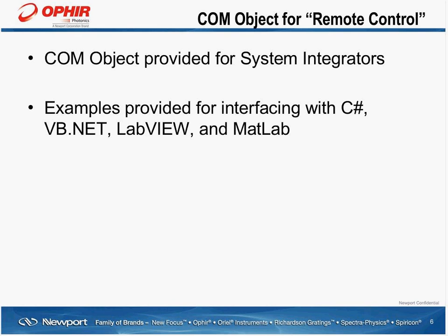I mentioned very briefly at the beginning, I'm going to mention it now slightly less briefly. The important feature of StarLab is the Ophir COM object. This replaces what used to be the ActiveX. Strictly speaking, and I'm not a software expert, this is not actually part of StarLab software itself, but philosophically, this is what enables users, for example systems integrators, to communicate with and control an Ophir instrument, StarLab, but not using StarLab, rather from within their own software.